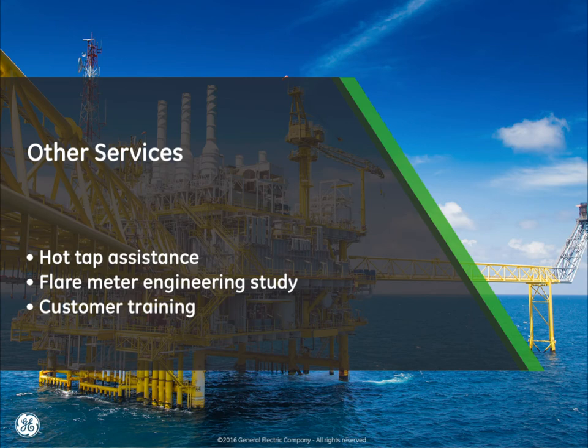To summarize, service is not simply for break-fix coverage. Although timely response and technical expertise are necessary for unforeseen product issues, ongoing preventative maintenance is essential to get the best out of your flare flow meter. Product capability is an important factor when considering future flare meter purchases, but service capability is an equally important consideration. So with that, I will pass it back to Randy for close.